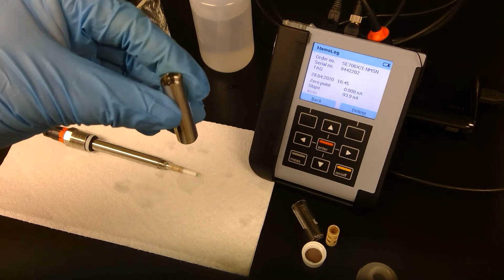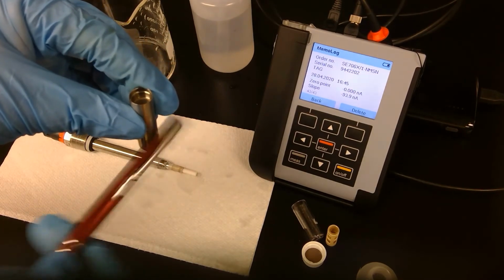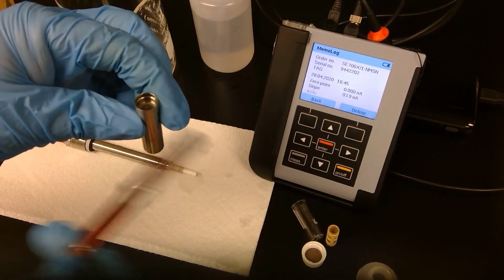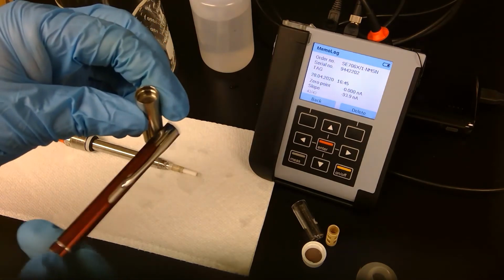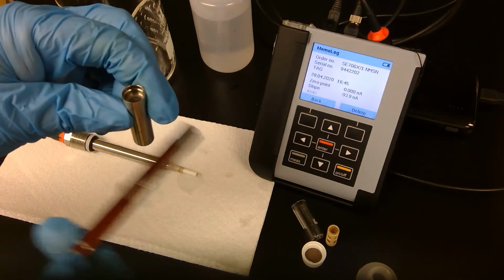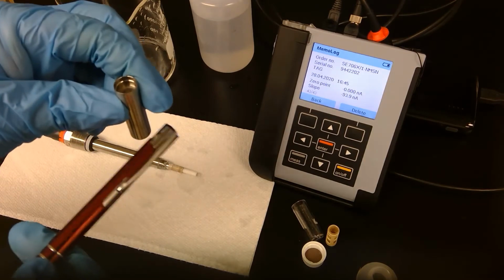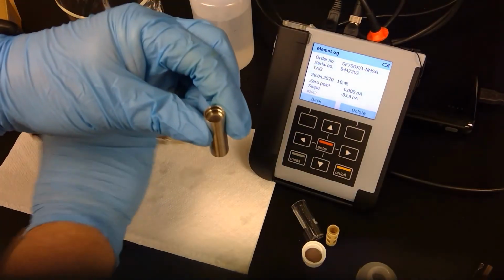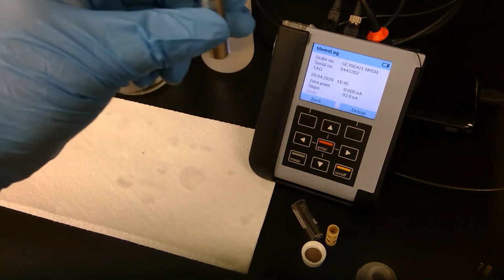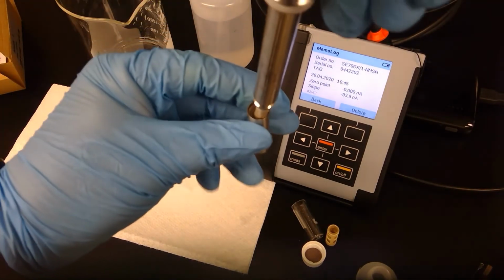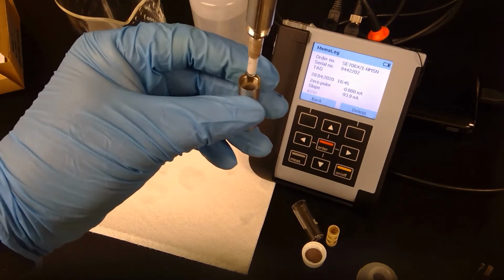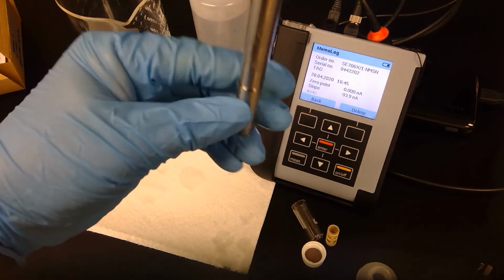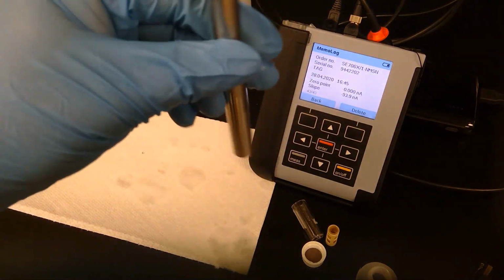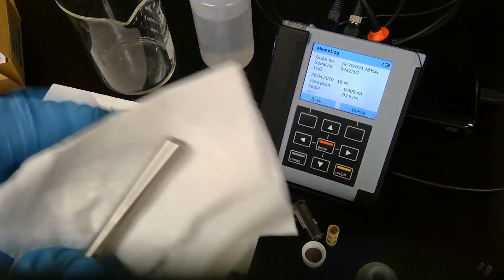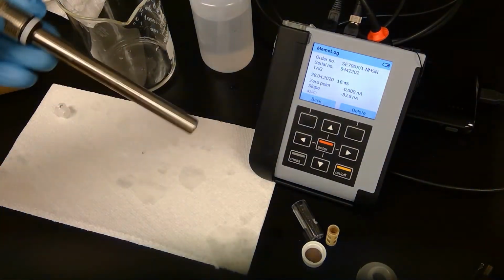So now that it's filled with new electrolyte, I just take a pen and lightly tap the sleeve. What I'm doing is making sure any air bubbles that were at the bottom of the sleeve come up to the top. So when I put the electrode back in, I don't have any trapped air, which would cause the measurement to drift. So I take the probe and I carefully insert it back into the sleeve and thread it together. Okay. So we've replaced the membrane, we've replaced the electrolyte.